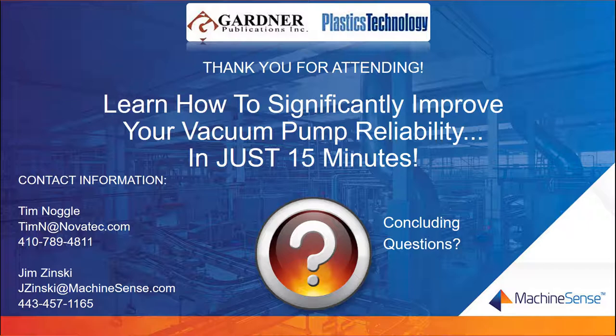Next question related to pump maintenance: does it matter if pump maintenance is done before starting to collect data? The data that it collects and the analytics performed will be the same regardless of whether pump maintenance is done, but to have a better understanding of what the conditions are that represent poor operating conditions — dirty filters, oil changes, and so forth — the deviation from that starting point is very important. So to be accurate with your predictive analytics, it is important to start out with as good a baseline as possible.